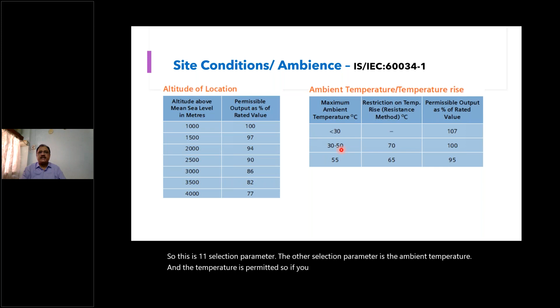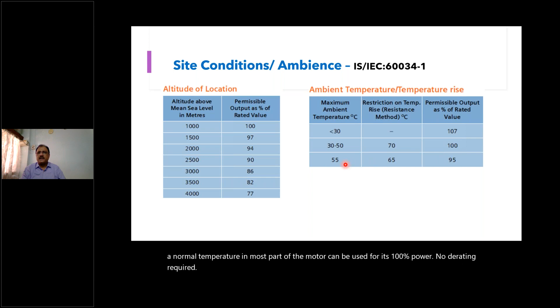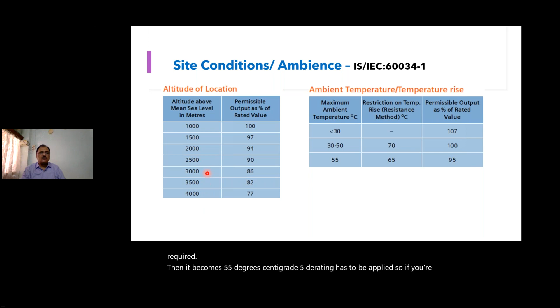So this is one selection parameter. The other selection parameter is the ambient temperature and the temperature rise permitted. If you have between 30 to 50 degrees centigrade, which is the normal temperature in most parts of India, the motor can be used for its 100% rated power, no derating required. When it becomes 55 degrees centigrade, 5% derating has to be applied. An industry which is 3000 meters high with 55 degrees centigrade is not possible, but you will find that the motor has to be derated according to altitude as well as according to the temperature rise. Wherever the temperature is below 30 degrees centigrade, it is possible to uprate the motor output to 107%. So these two are very important for understanding.